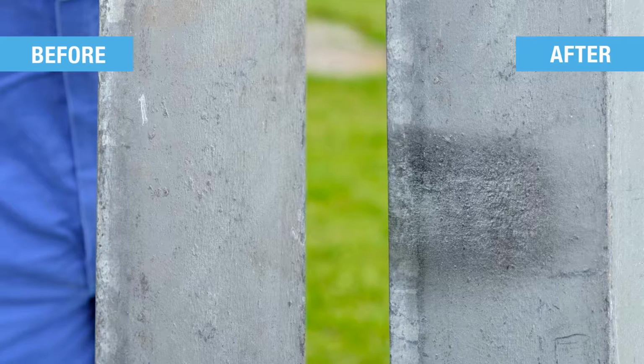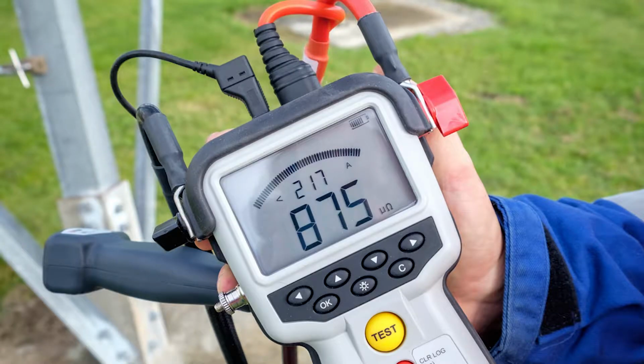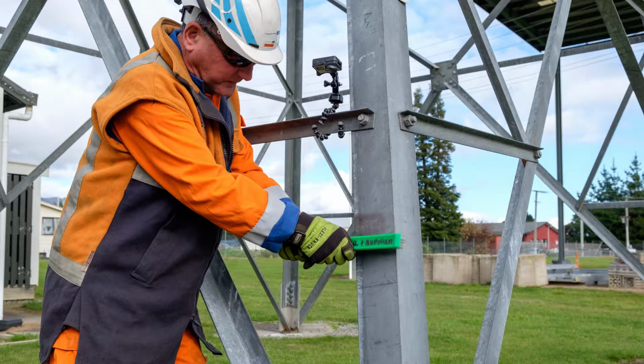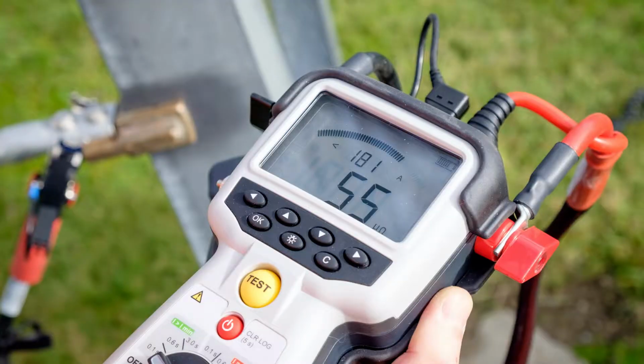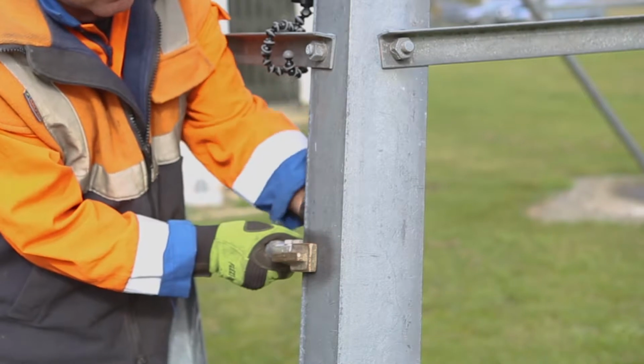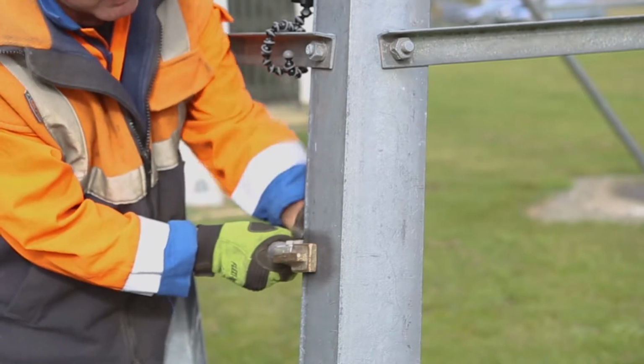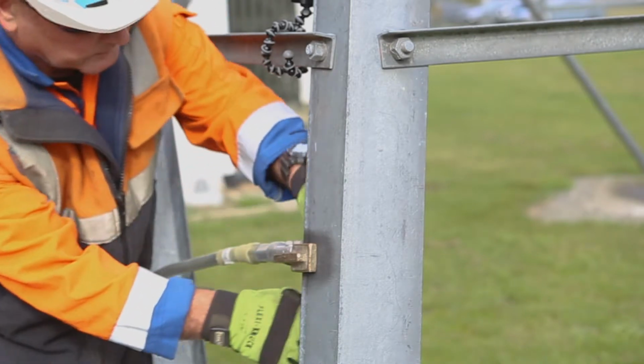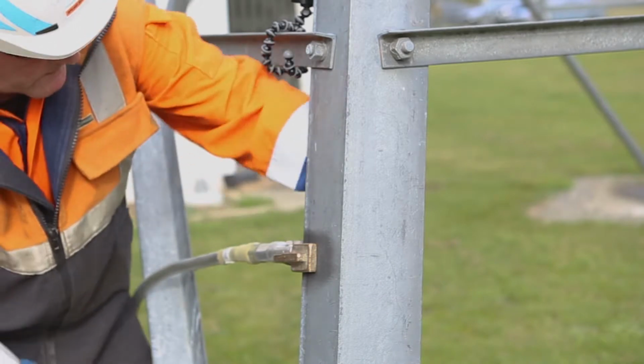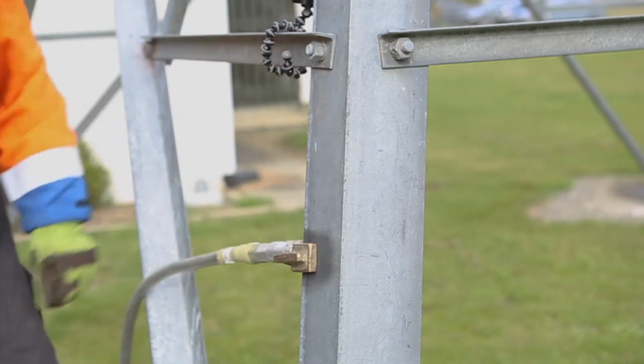You're probably wondering how much of a difference cleaning actually makes. Here are the results of a test on a tower leg before cleaning and the results after a simple clean with a wire brush. Remember, even if the surface looks good, it may still need a clean before attaching the tail clamp. The key is to have a bright, shiny surface.